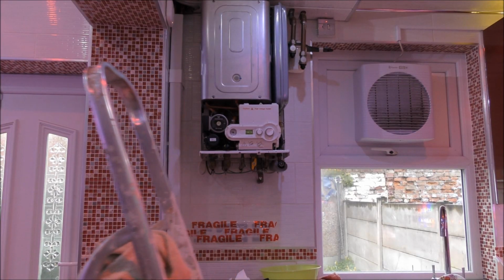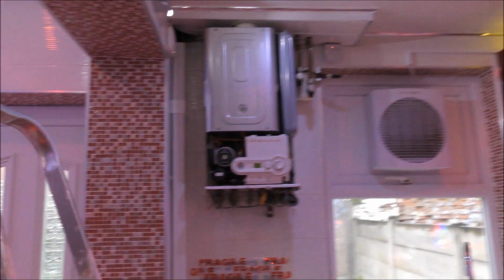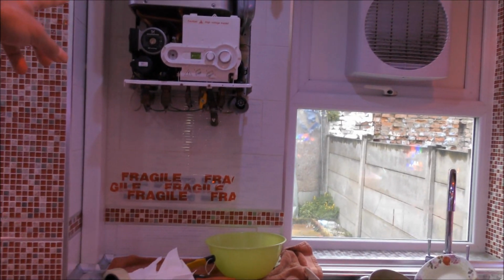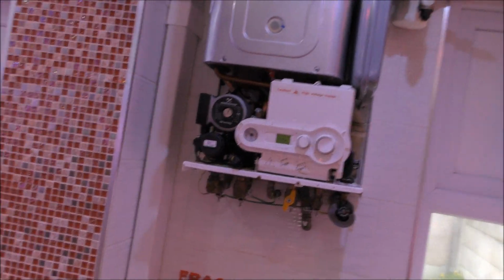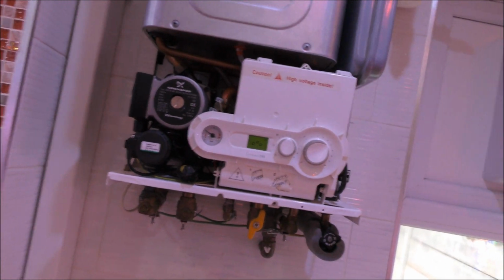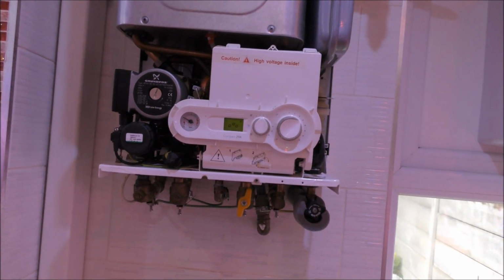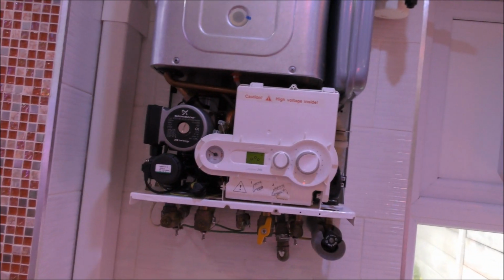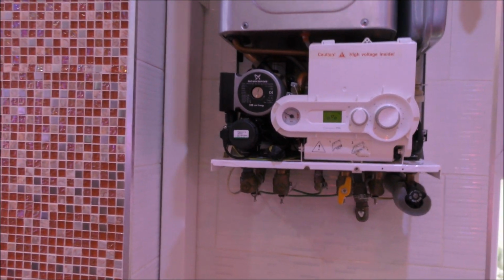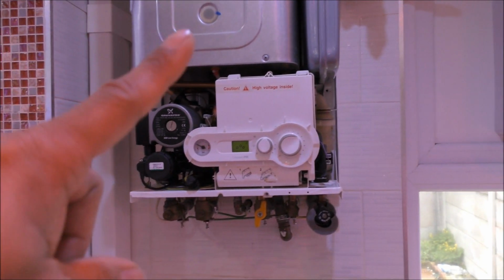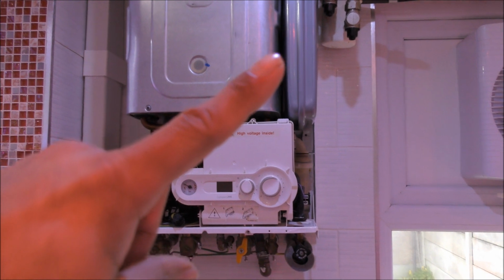On the final note, I've shown you how to get rid of all the crystal build-up, and the unit is calibrating itself now. I've changed the thermistor. I don't think the old one was too bad, but I replaced it anyway. And there's 1 bar of pressure on the expansion vessel.